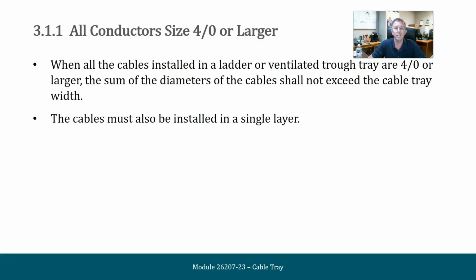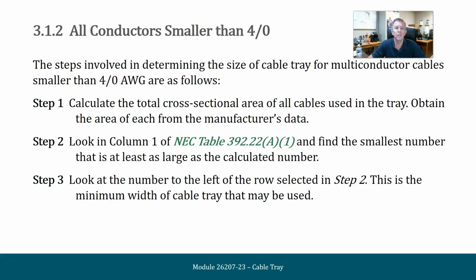All conductor sizes 4/0 or larger. When all the cables installed in a ladder or ventilated trough tray are 4/0 or larger, the sum of the diameters of the cable shall not exceed the cable tray width. The cable must also be installed in a single layer.